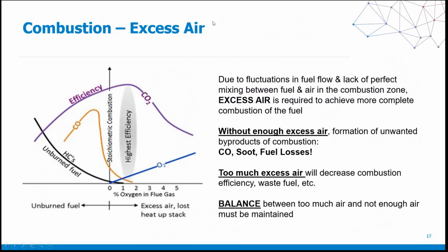And when we talk about combustion, as I just touched upon, we want to discuss excess air. Excess air, by definition, is due to fluctuations in fuel flow and lack of perfect mixing between fuel and air in the combustion zone. Excess air is required to achieve more complete combustion of the fuel. Without enough excess air, formation of unwanted byproducts of combustion is created.